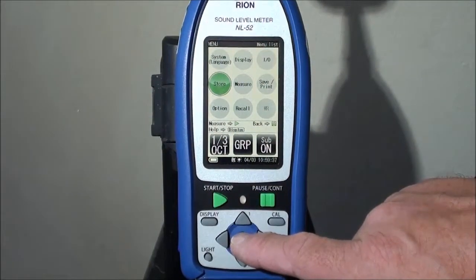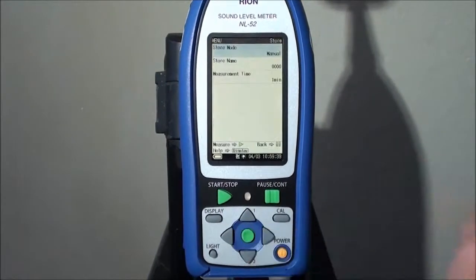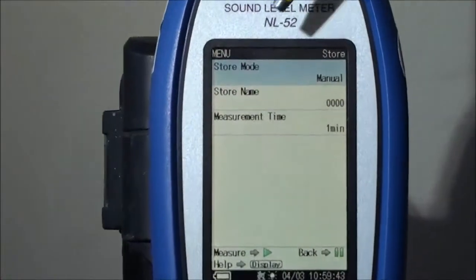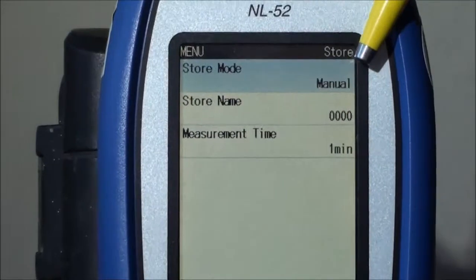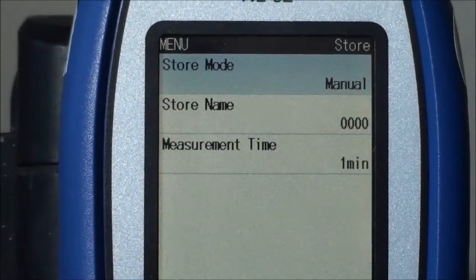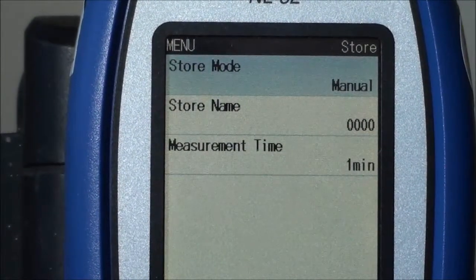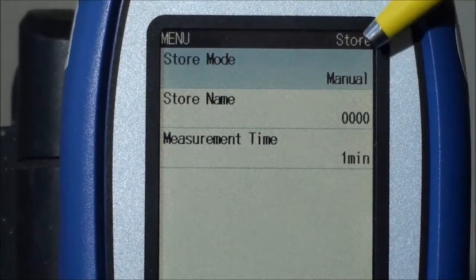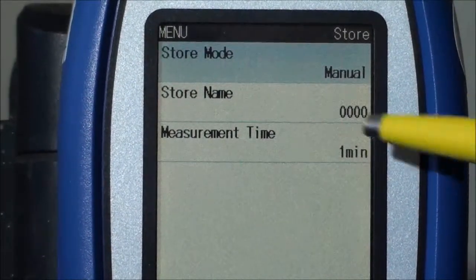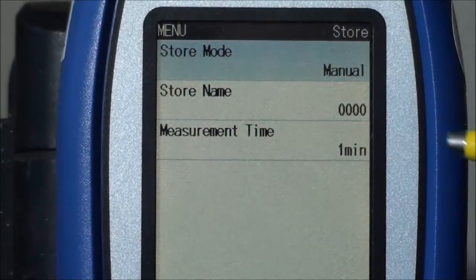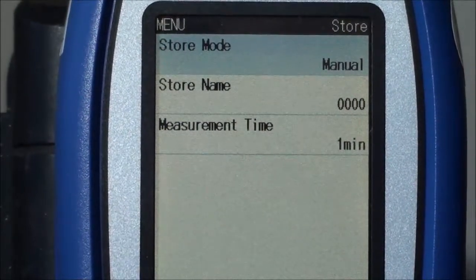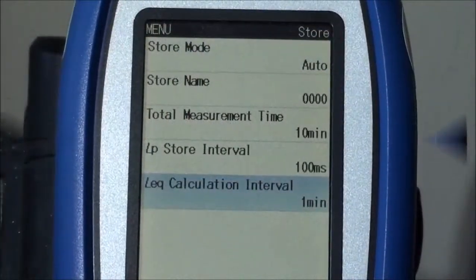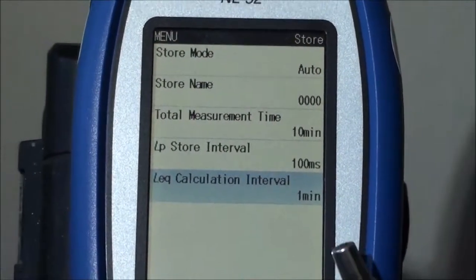Everything you need to know about how storage of data will take place on the instrument. In your particular case, I would advise that most of the time you use manual storage, which means you make one measurement at one location and you press save. That will store into a store name that you've selected and will increment the file every time you press store.